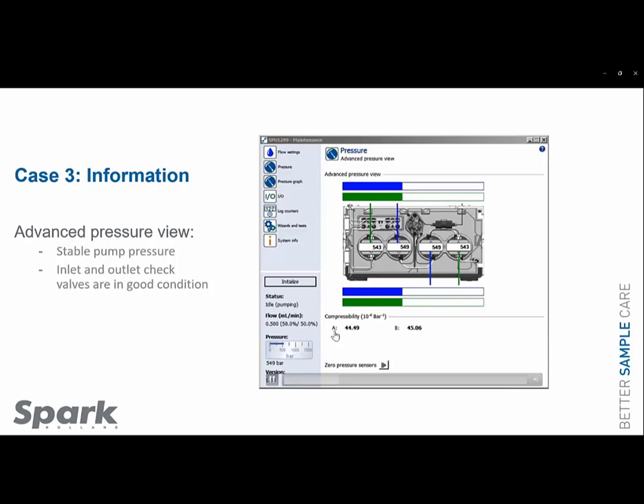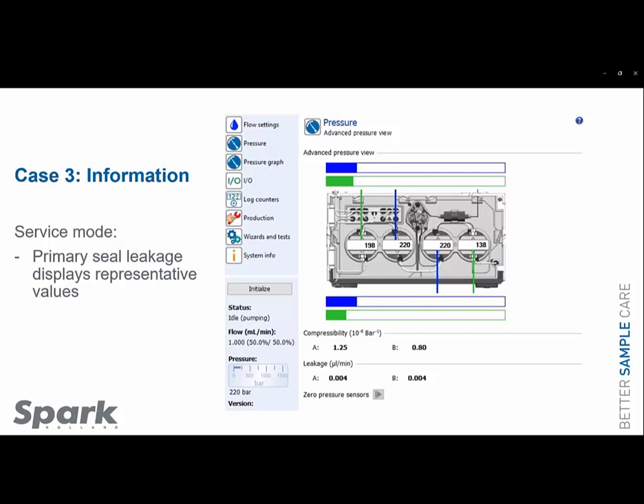We see a compressibility value, both similar, and we pump with mobile phase. Pump A and pump B are equal. So the pump is running fine in this screen. That also means that the inlet and the outlet check valves are okay. I'm convinced about that. What we also noticed in the pressure view in service mode, there's a leakage value in here.